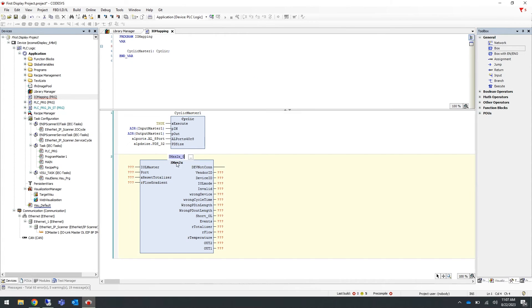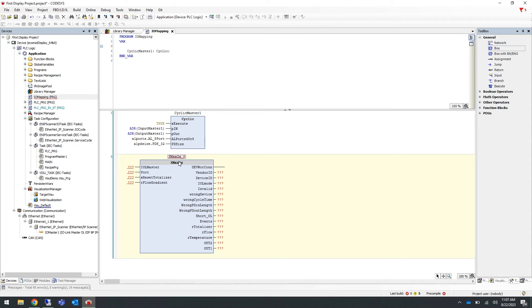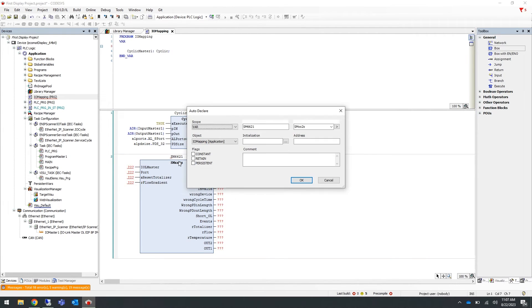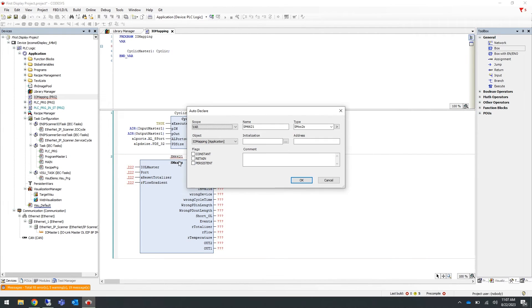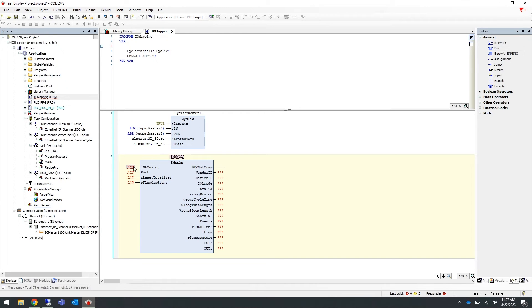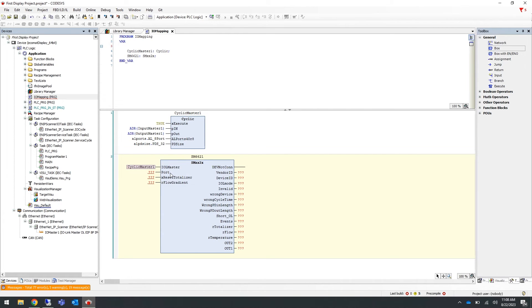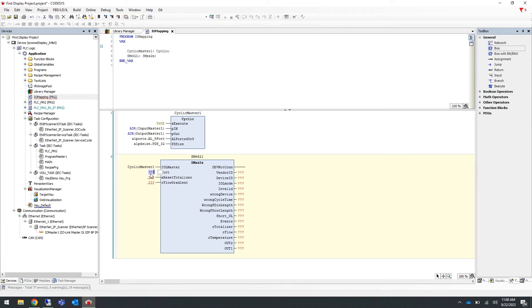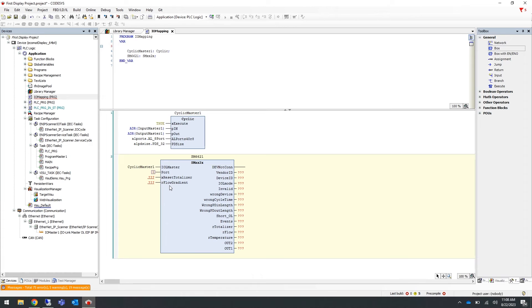Press enter and give it a meaningful name, and press OK. Now we point the IO-Link master variable to the cyclic function block we just created, so this will go to cyclic master 1. The port is pointing to the port number that the SM is connected to. In our example it is connected to port 1 so I'll press 1. Then you need to enter the flow gradient for the SM6621.